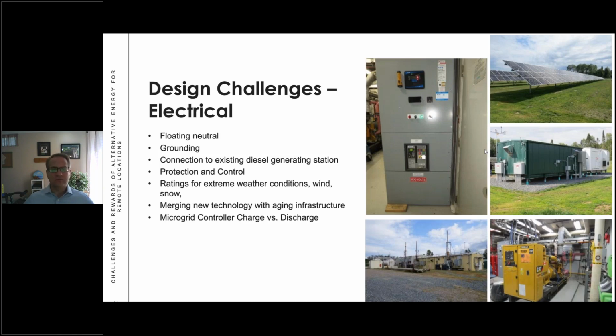And the grounding of the system was a challenge too because of the silty soils. We added some additional copper and grounding rods to achieve the proper equipment grounding that we needed, and also to ensure that personal safety requirements in terms of step and touch potential safety concerns were met. Connecting the existing diesel grid station was also a challenge, and Hydro One Remotes helped us, or asked us rather, to help them connect up the microgrid to their existing diesel generating system and then connect it out through to the community.